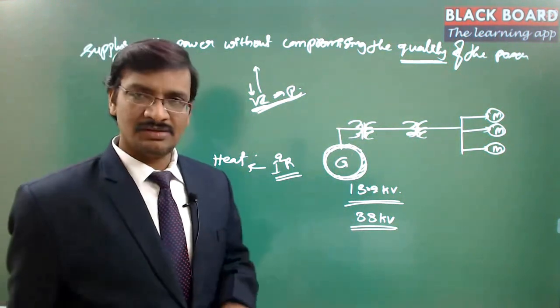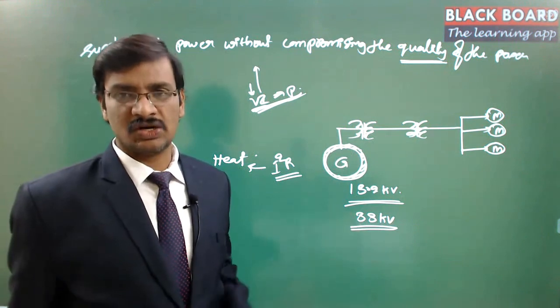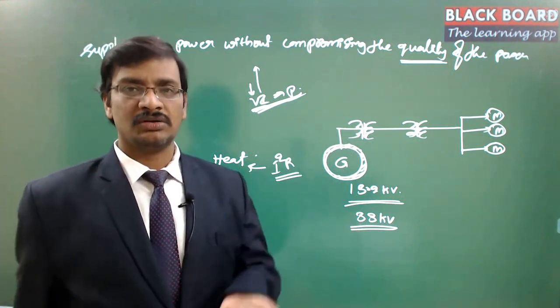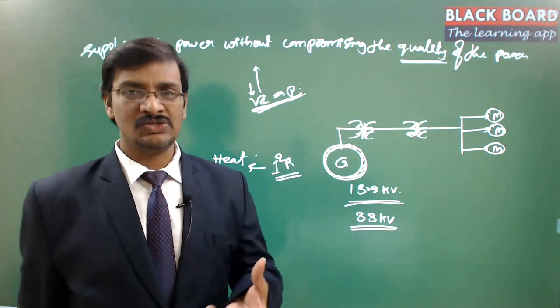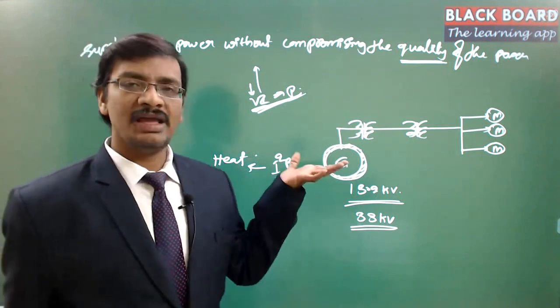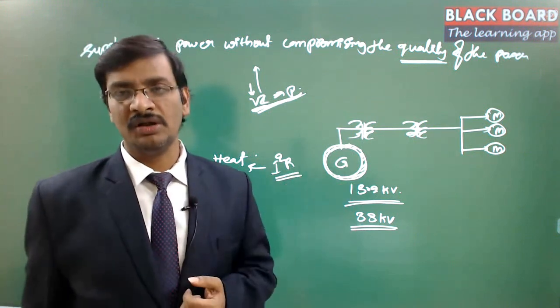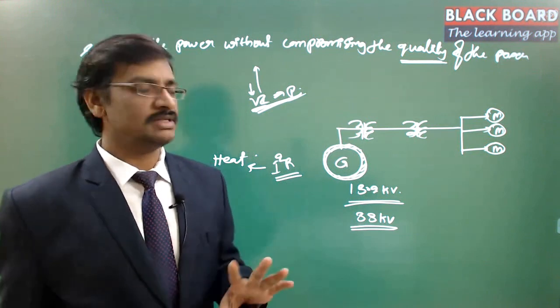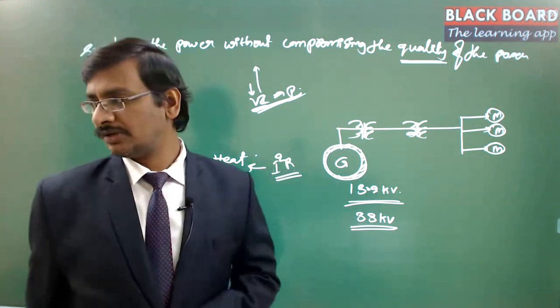This cooling process is fairly easier and less costly than increasing the insulation capacity. If you generate a higher voltage, the insulation has to be more, which would be a very costly affair. That's why we go for this particular scenario.